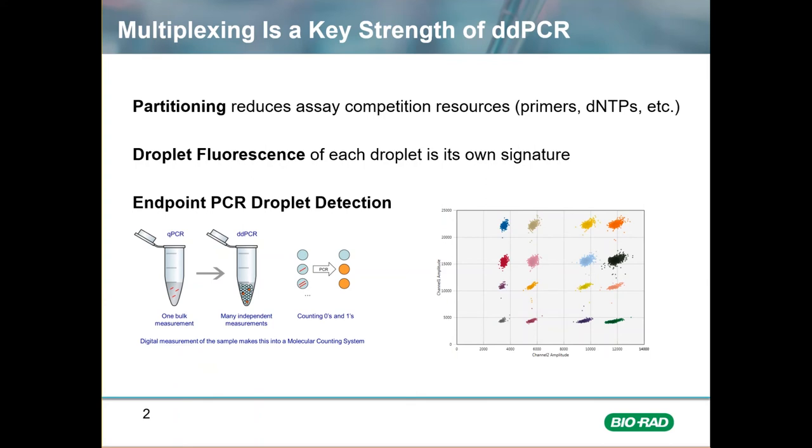Partitioning of the sample creates a unique situation where the assays do not have to compete for the PCR resources like bulk resolution multiplexing does. The more partitions, the more assays that can be multiplexed. Each droplet partition will have its own fluorescence, allowing for many more possible positive clusters to be identified clearly.